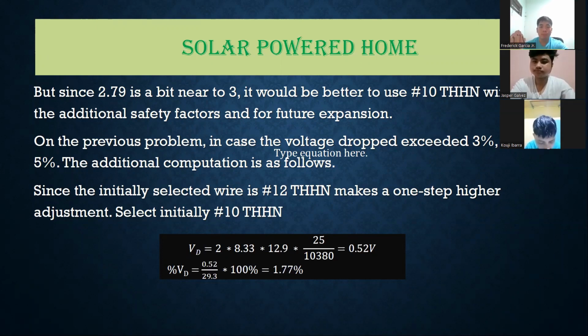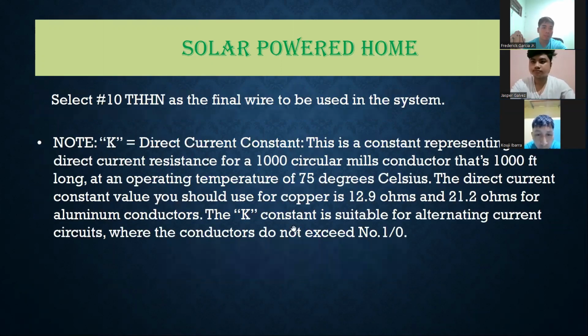On the previous problem, in case the voltage drop exceeded 3%, to let's say 5%, the additional computation is as follows. Since the initially selected wire is number 12 THHN, we make a one-step higher adjustment and select number 10 THHN. So we make the previous calculation for the voltage drop again. We get 0.52 volts. And for the percent voltage drop, we just divide that again by the voltage of the photovoltaic cell, times 100%, and we get 1.77%. So the selected number 10 THHN wire will be the final wire to be used in the system.